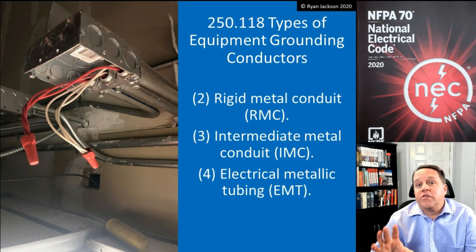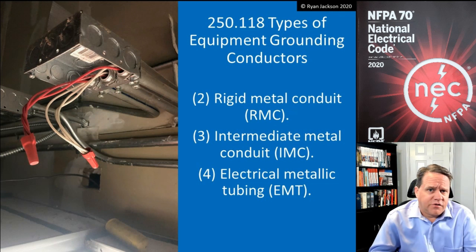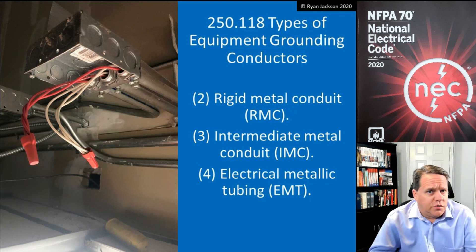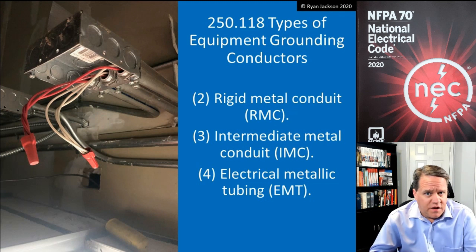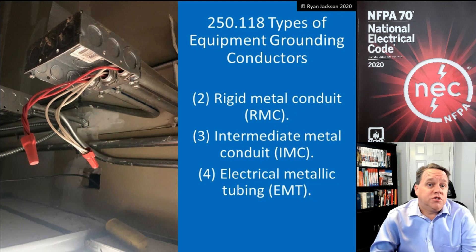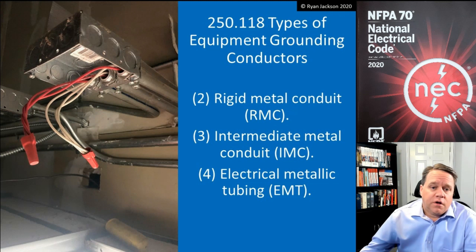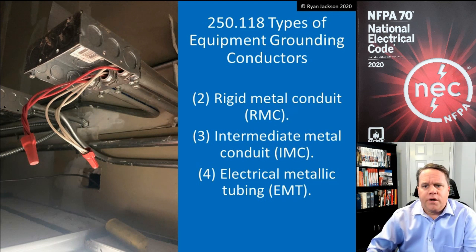I think you should put a green wire inside of your pipes, but it's not a requirement in the NEC. We can use rigid, IMC, and EMT as the equipment grounding conductor. There are some instances where you might have to do something extra — 517.13 comes to mind if you're wiring healthcare facilities in a patient care space — but speaking in generalities, you don't need a green wire inside of your non-flexible raceway.